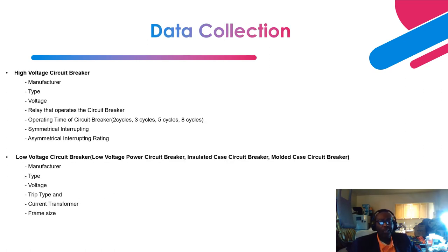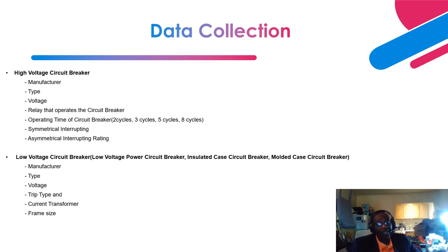For a high voltage circuit breaker, you need the manufacturer, type, voltage, the relay that operates that circuit breaker (since the relay output operates the trip or close coil), documentation on that relay, and the operating time — two, three, five, or eight cycles. Most often, high voltage circuit breakers are two-cycle breakers; medium voltage is three- to five-cycle. You also need the symmetrical and asymmetrical interrupting ratings — the asymmetrical rating is typically the peak short circuit rating of the circuit breaker.